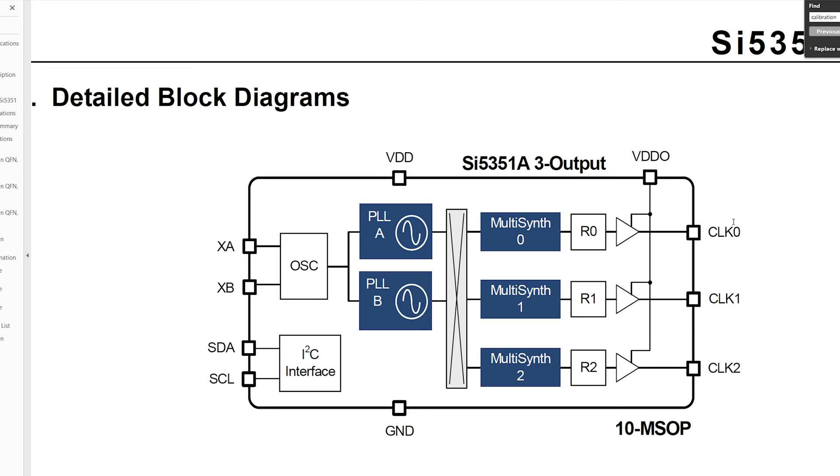So how to fix this? There's a routine and basically I believe it's inside this oscillator there's some registers and we can address them and we can correct the frequency at this point. And if we do that as it goes through its calculations on the Arduino and it sends the information up, this will multiply, this will divide and we'll get the correct frequency coming out here. So that's basically it, that's all we need to do. So let's move on to the calibration routine.